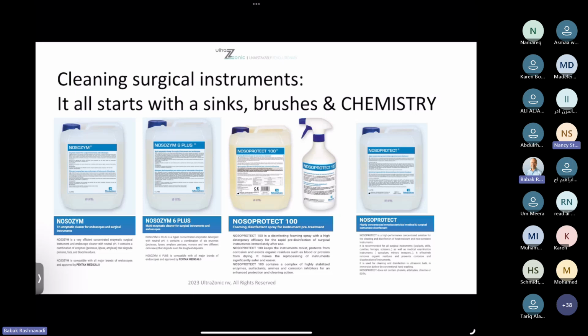good cleaning. In ultrasonic cleaning, when you have a weakly working ultrasonic cleaner, what we see in the market is that you use enzymatic detergents in your ultrasonic device. And to be honest, at that moment you count on your enzymes to succeed in a good cleaning. But that actually also means that your ultrasonic device is too weak. It's not good enough to clean the instruments by itself.